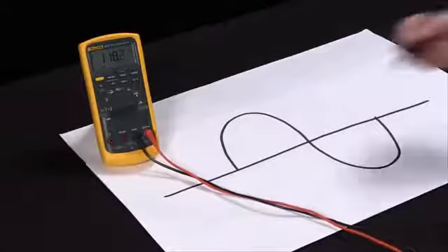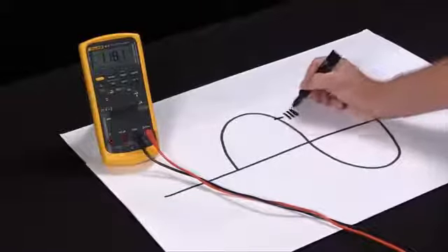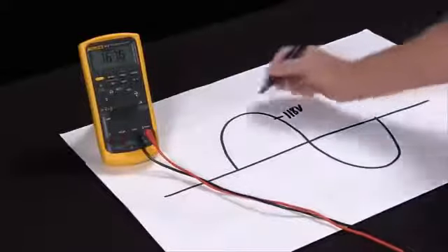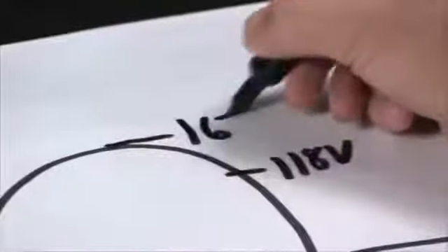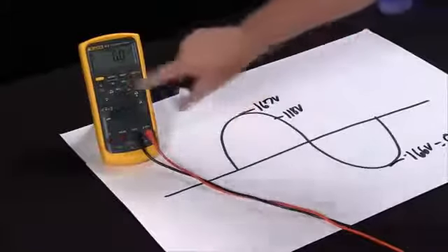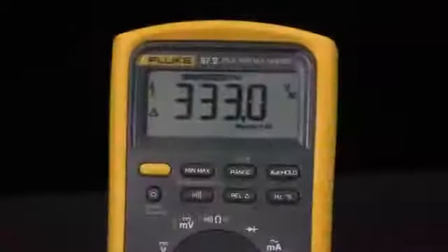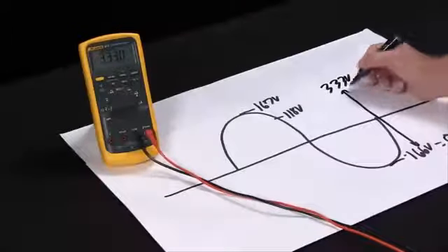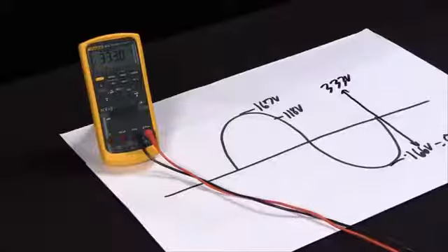Right now, we're looking at 118 volts, which is the RMS value of this sine wave. If I hit the peak min max mode, now with the fast peak mode, I can actually measure the peak at 167 volts. And with min max, I can hit that, and now I hit the negative 166 volts. Where the relative mode comes in is I can now make this negative a 0. So if I hit relative, that becomes 0, and now I'm measuring the peak to peak of 330 volts of this sine wave by using a combination of the fast min max and the relative mode.